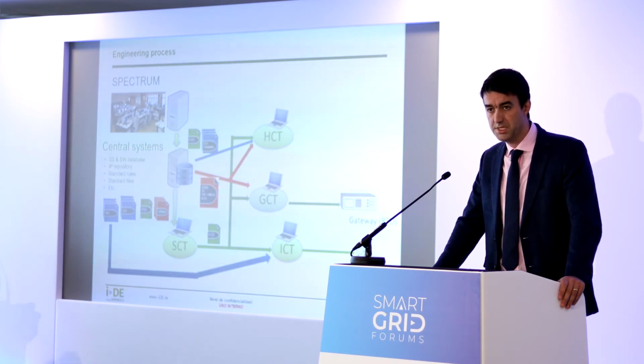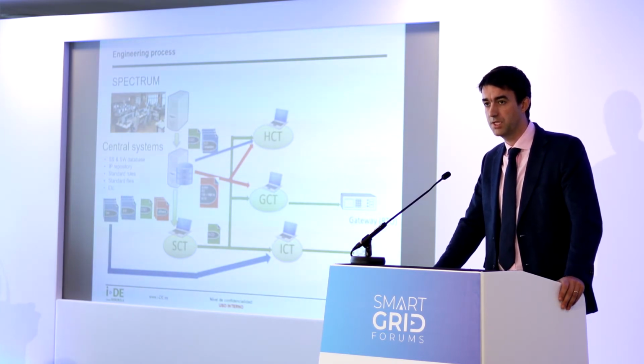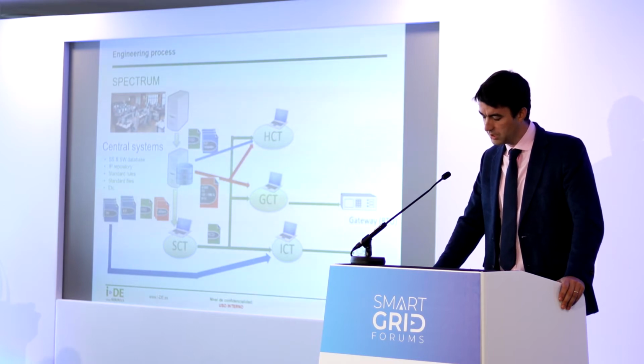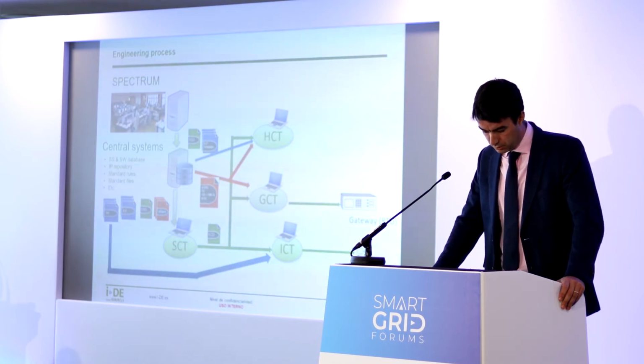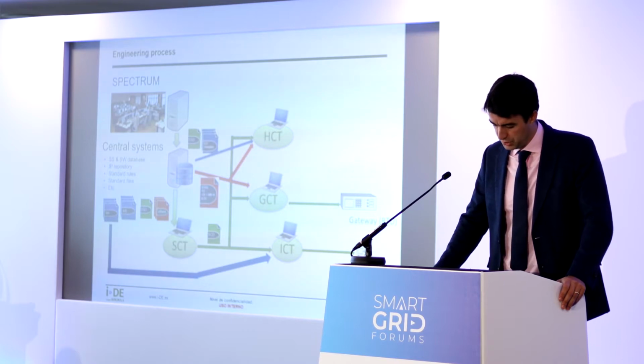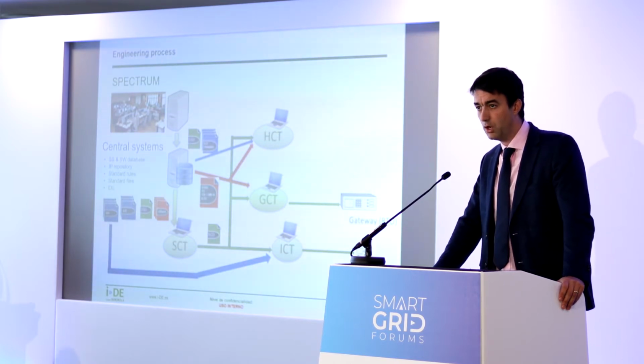And of course, this is dependent on a high level of standardization. We have standardization per bay type, which includes not only the data sets, the GOOSE messages, and report control blocks for each IED, but also the standardization of the telecontrol signals and the HMI representation for that bay. This means that we will use ICD templates, which will be more like IID files without the IP address and the IED name. And we will use all this information to create one big input for the SCT tool.